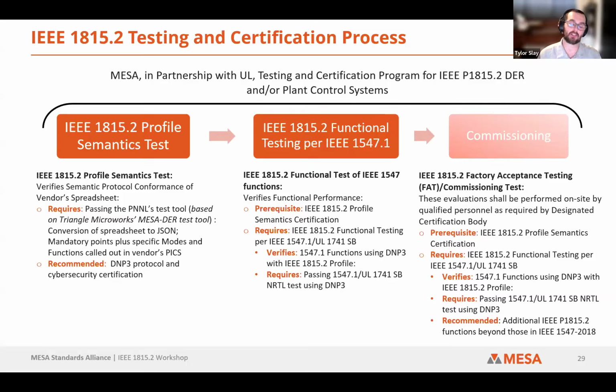Then you get into the functional tests. You need to have that semantics done, and then this is where we tie into the 1547, 1741 SB testing that's already predefined. 1815.2 is a superset of 1547 UL 1741 SB, so all of the requirements there are still required in 1815.2. If you pass all of those, you become certified for 1547. And when we release the additional 1815.2 functions, also outlined on the right-hand side of slide 11, where you have all 21 functions, then you would become 1547 compliant and 1815.2.